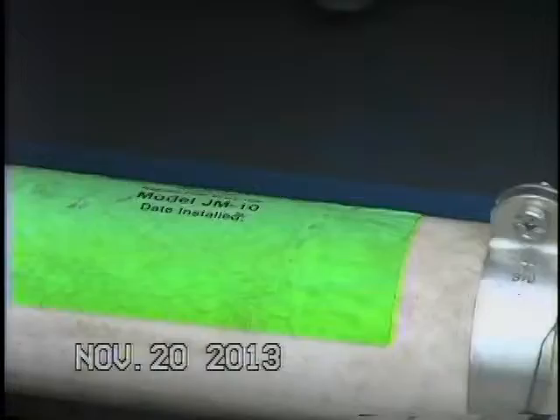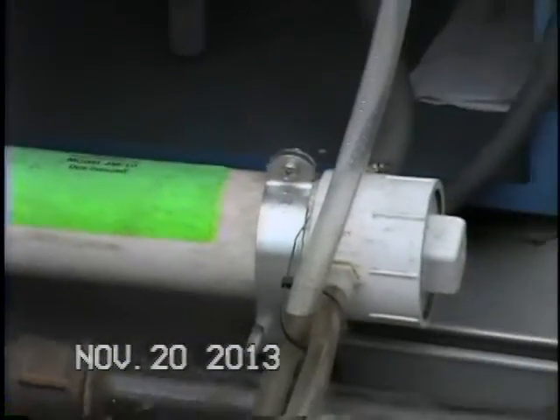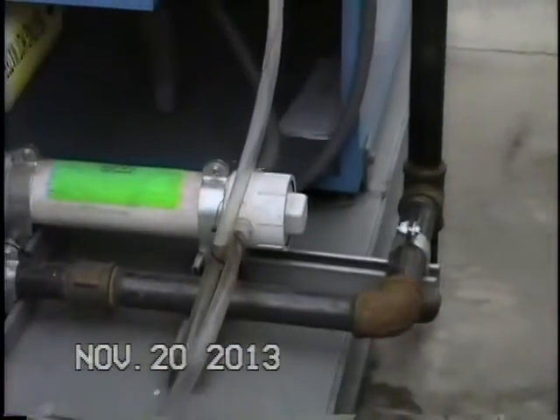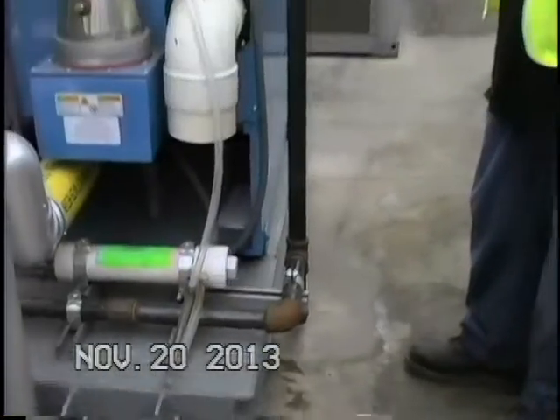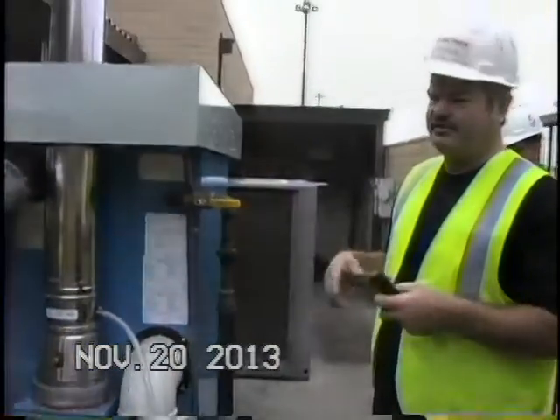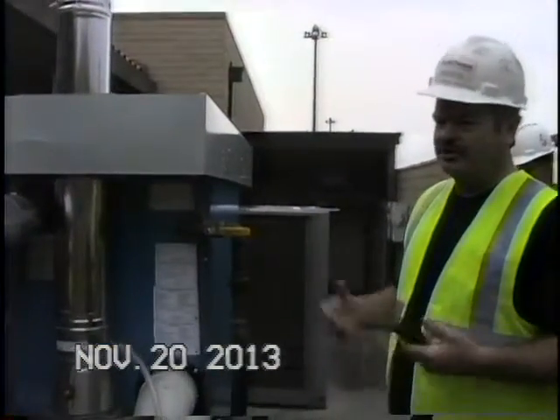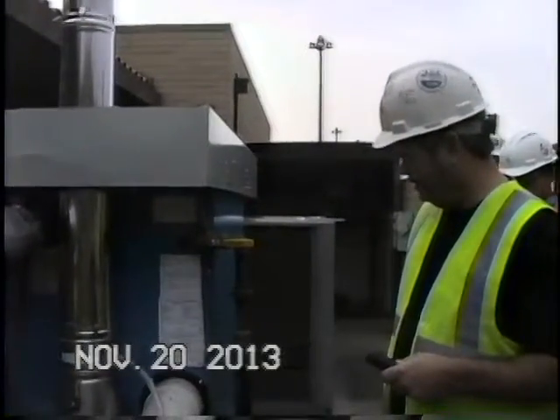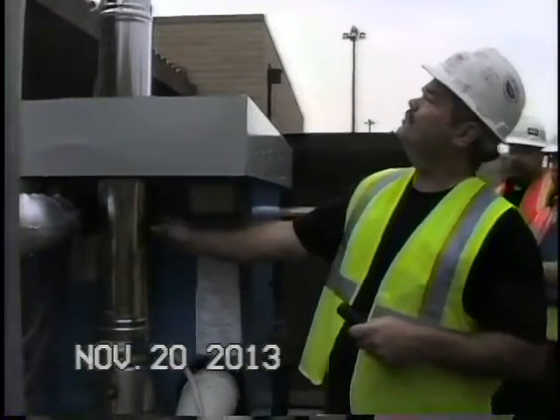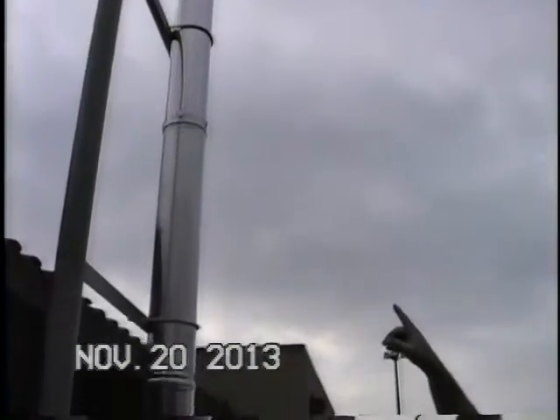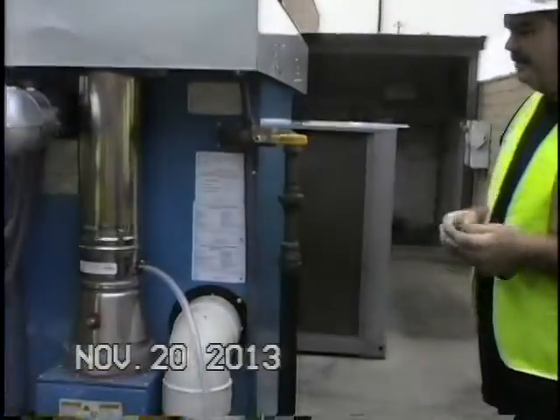Is that in the O&M manual? Yes. That's the neutralizer I talked about. We call it a neutralizer. And you can test the water coming out of there. If it's too acidic, you know your limestone's all deteriorated. Here's your flue. And it was raised above the roof line because otherwise it would downdraft and do some weird stuff. So that's per the O&M.